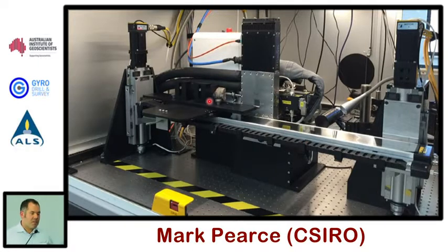Now, instead of being a conventional X-ray tube where you have a solid target, which over time kind of drifts and causes beam instability, this system actually uses a liquid alloy, which it pumps through this tube inside this jacket here, and down the back. It's then hit by an electron beam and produces the X-rays.